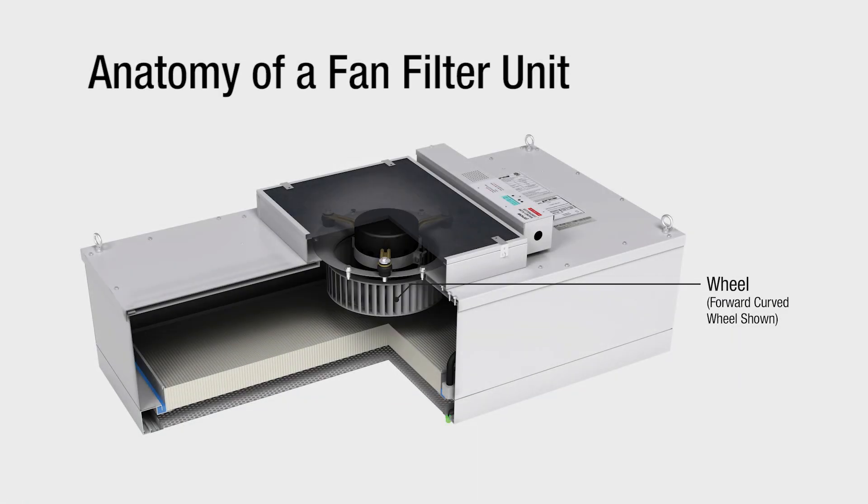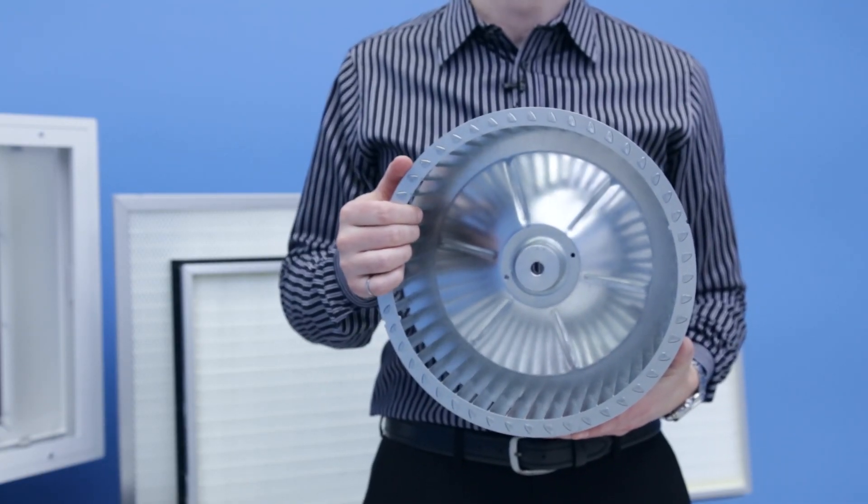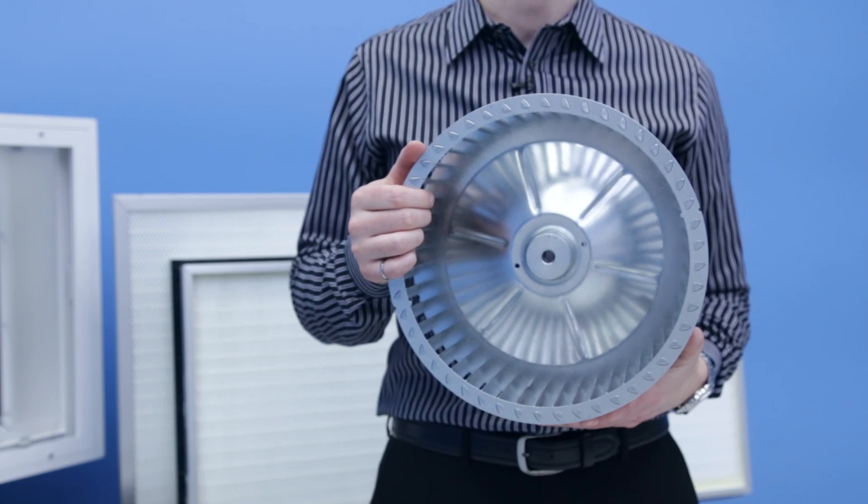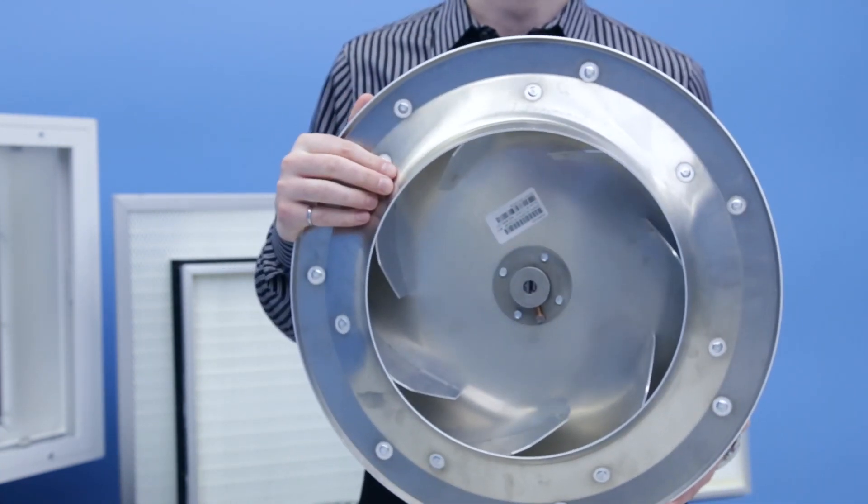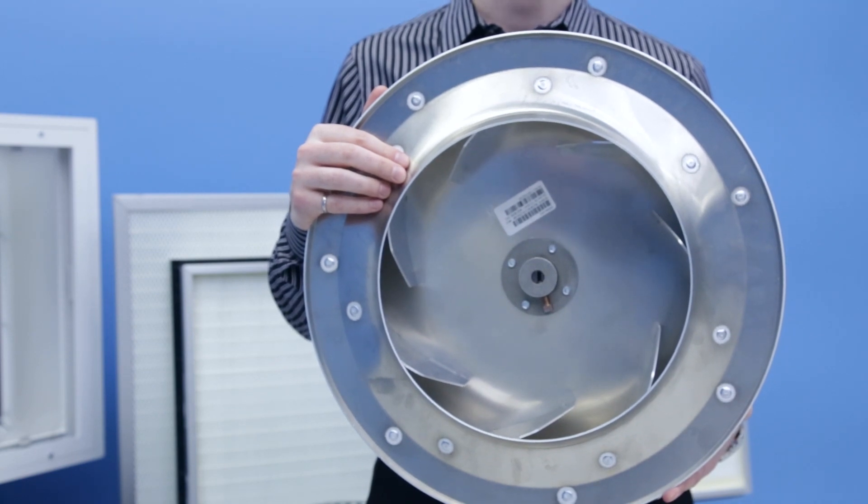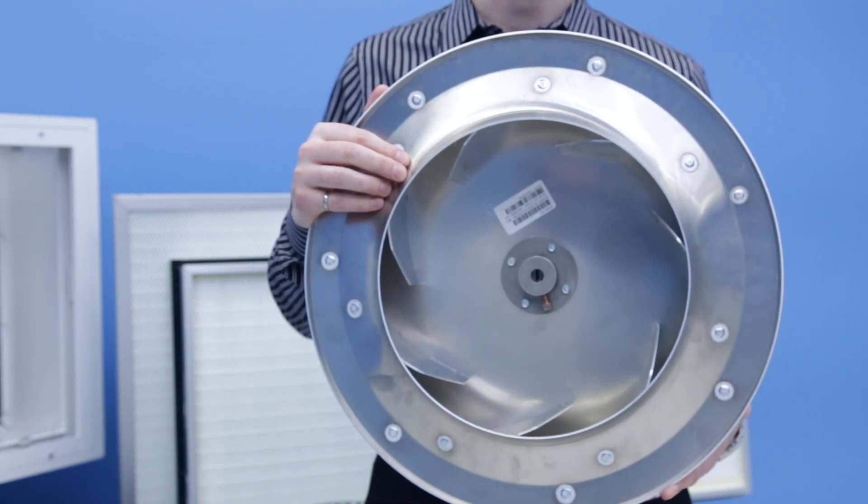In addition to motor options, there are also two wheel options. Forward curved wheels are the standard option and are compatible with the EC motor and constant flow program. Backward curved wheels, although not compatible with the constant flow motor program, are a more energy efficient option.